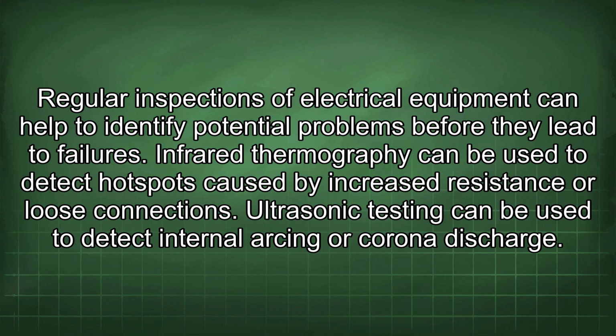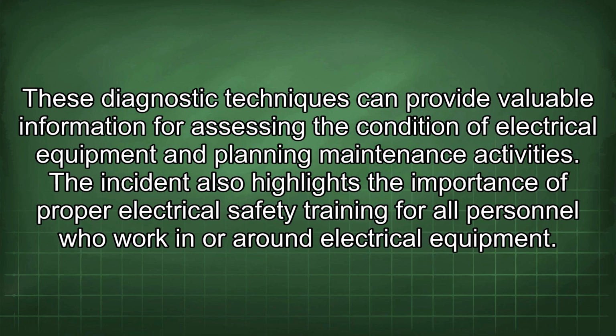Infrared thermography can be used to detect hotspots caused by increased resistance or loose connections. Ultrasonic testing can be used to detect internal arcing or corona discharge. These diagnostic techniques can provide valuable information for assessing the condition of electrical equipment and planning maintenance activities.